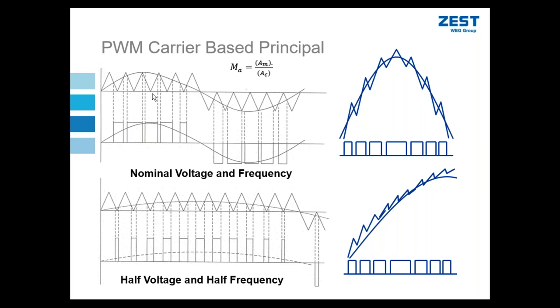So just to get back to this term modulation index. When my sinusoidal waveform is at its nominal condition, in this case 50 hertz, my carrier signal amplitude can be the same because I want it to be maximum. So the ratio between the amplitude of the sinusoidal signal and the amplitude of the carrier signal, when that is at one, that is when I'm supplying maximum speed and maximum voltage to the motor, then my modulation index is one.